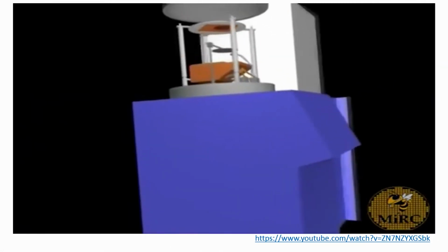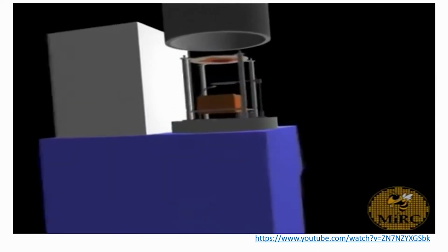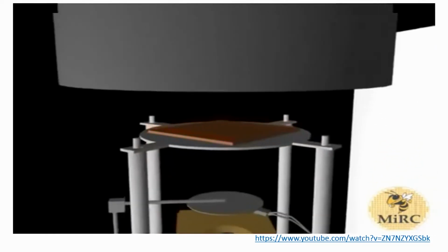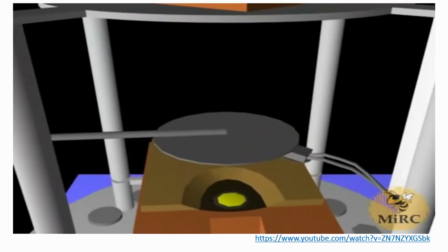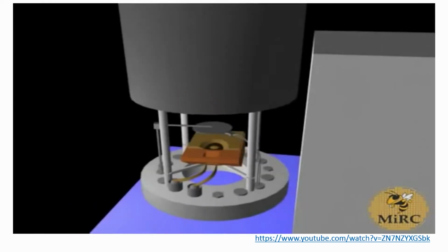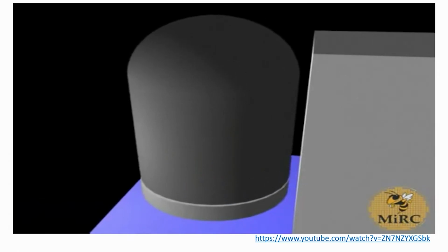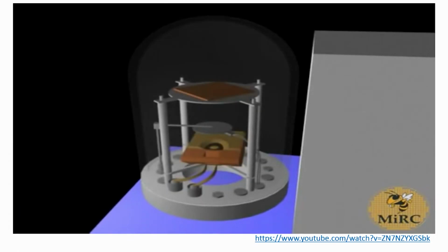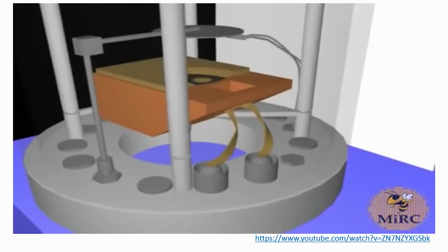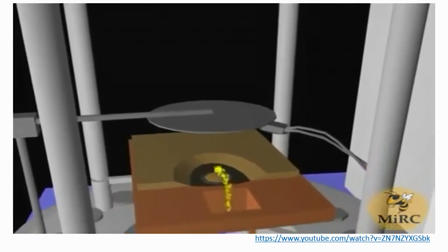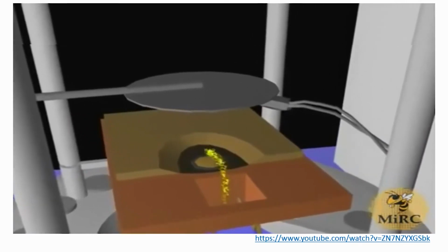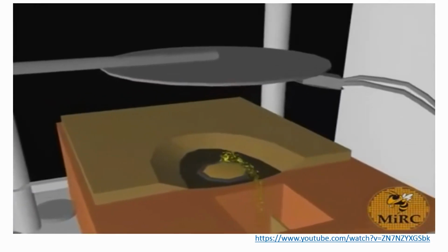An electron beam evaporator, a type of physical vapor deposition tool, is used to coat one side of a sample with various metals. Commonly used metals on this machine include aluminum, platinum, gold, chrome, nickel, copper. Once a sample has been loaded, the chamber will be closed. The chamber is then pumped down to a very low pressure. The machine then releases electricity through a filament. Several magnets are used to direct the electron beam from the filament to a crucible containing the target metal.